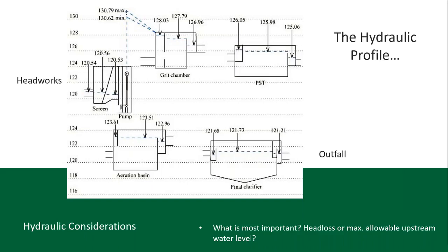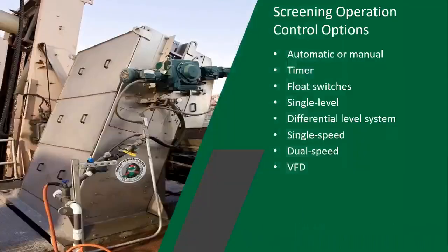That 10% difference in head loss is reasonably attributed to the design differences. However, if you're working with various manufacturers and one's demonstrating a head loss figure that's 30 or 50% less than all the others, it should give you pause to ask more questions, because sometimes what seems too good to be true actually is.